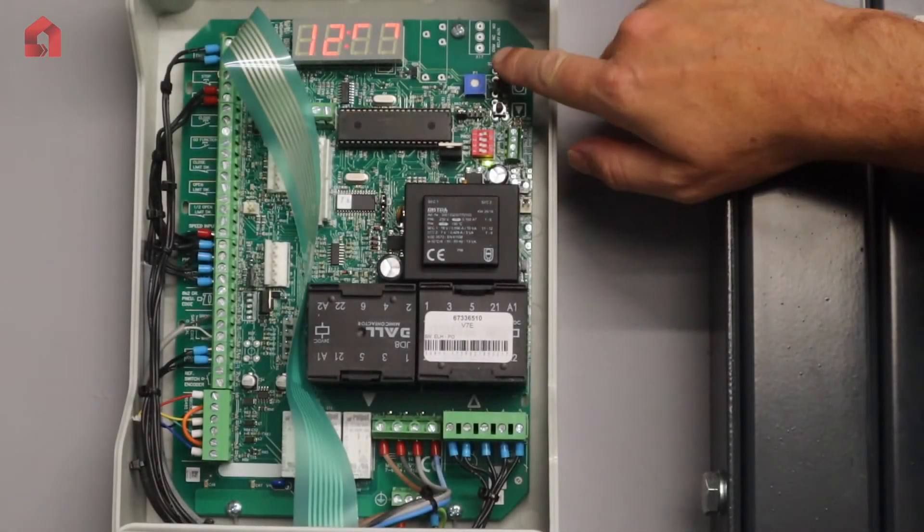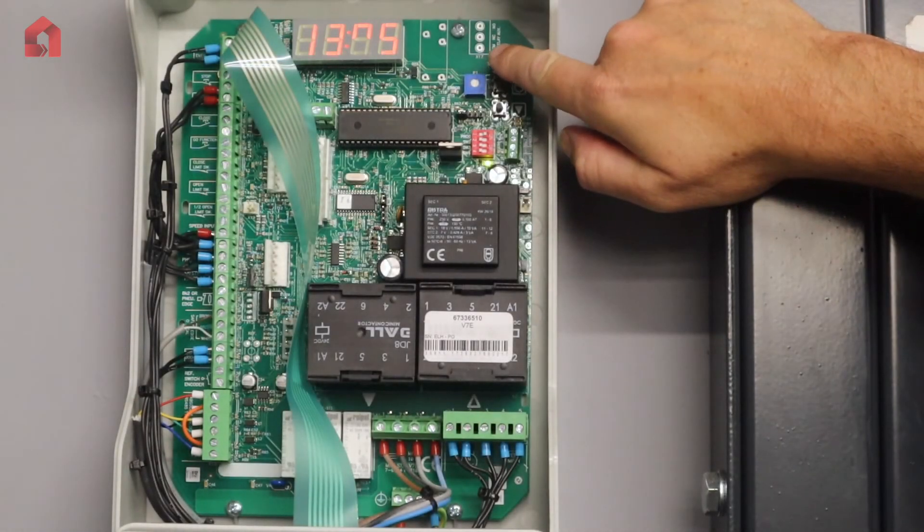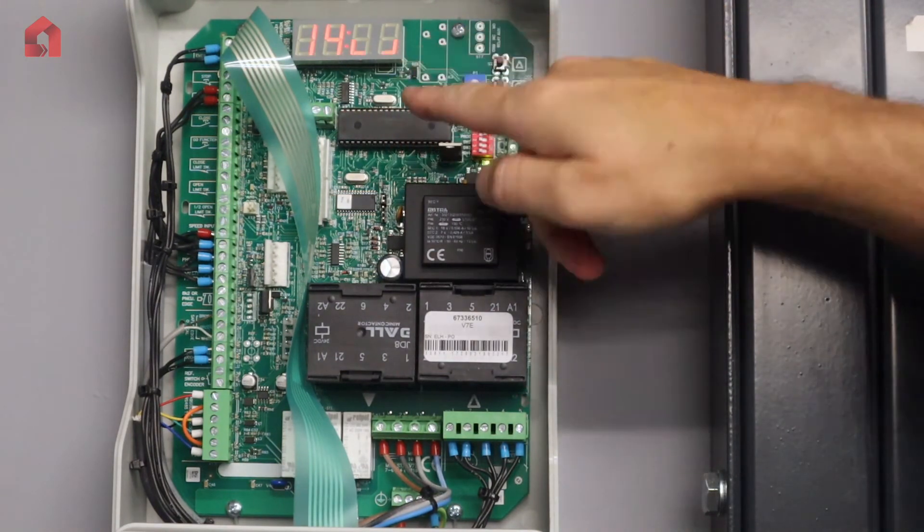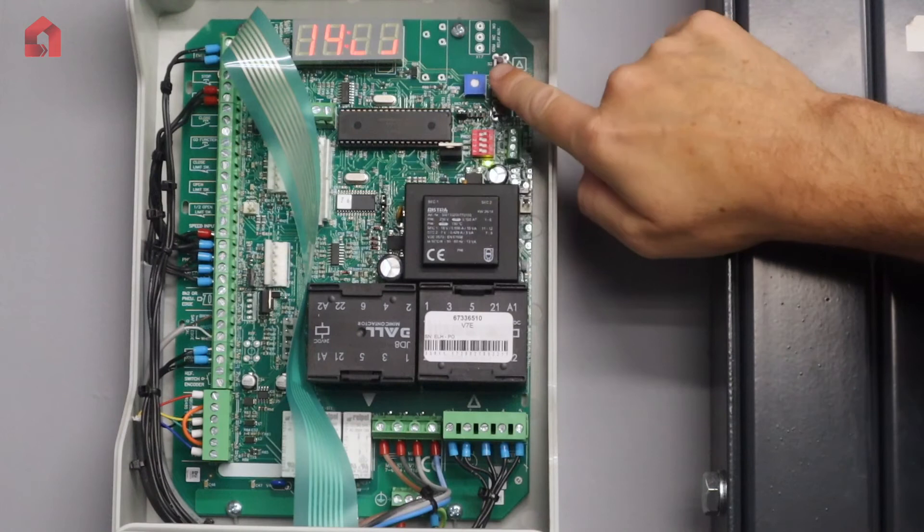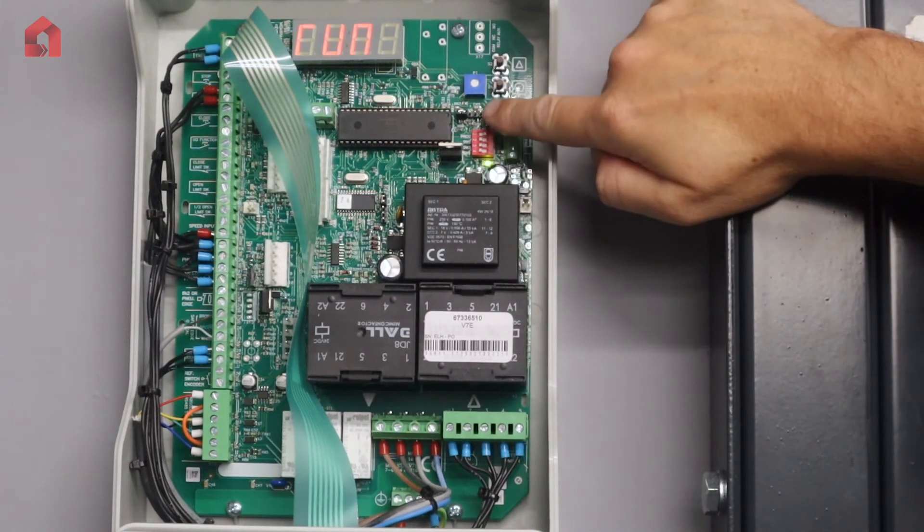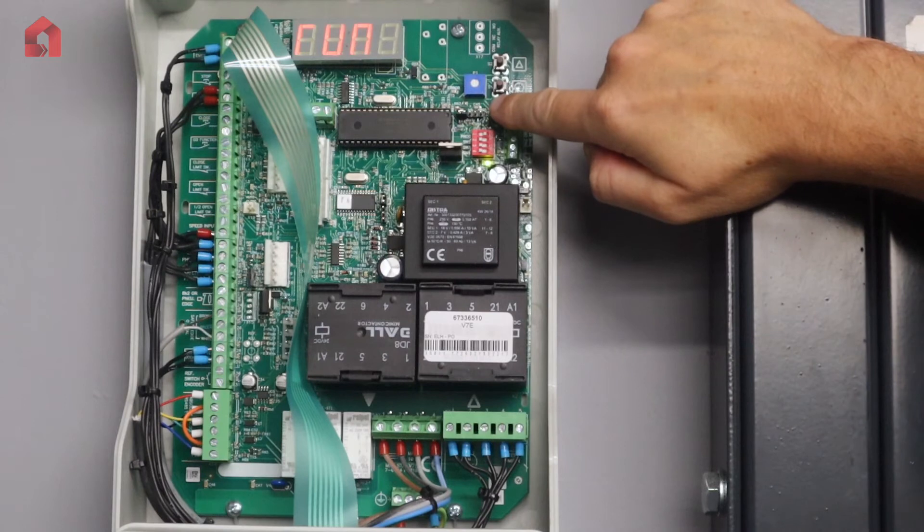So to set the bottom limit, if you then scroll up to parameter 14, it shows your bottom limit there. Press your stop saying do you want to set your limit? Yes. Press the stop once more, it will say run. So you now run it down to where you want to set your bottom limit.